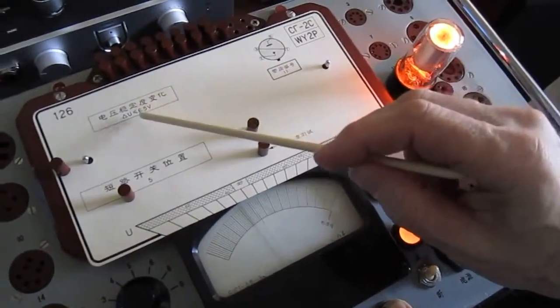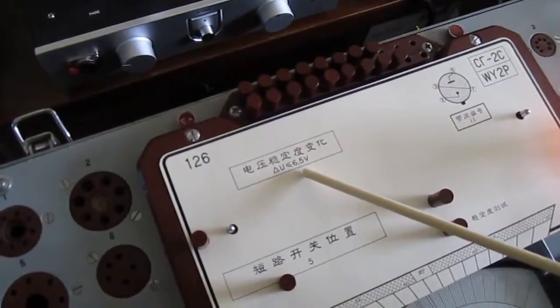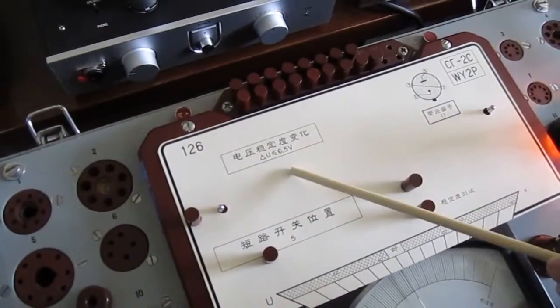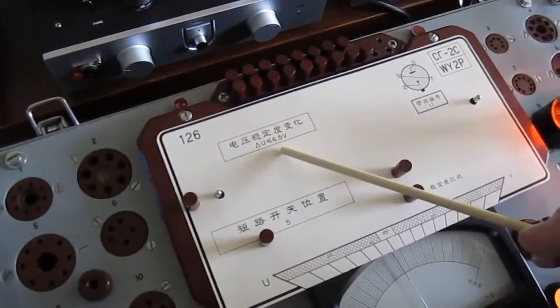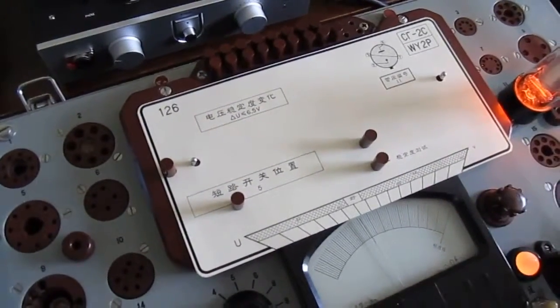And what we're looking for in this particular tube is that the voltage drop should be less than 6.5 volts. I think the specification in the U.S. may be closer to a voltage drop of 4 or 4.5. But for the Chinese tubes, this is what the specification is.